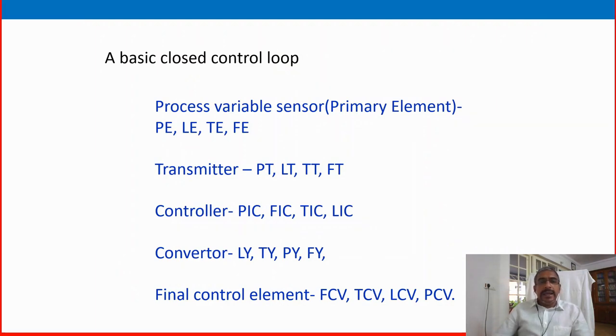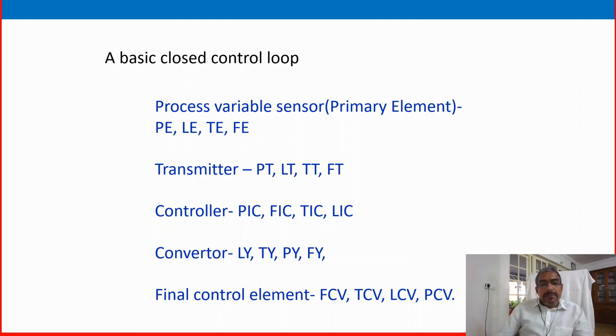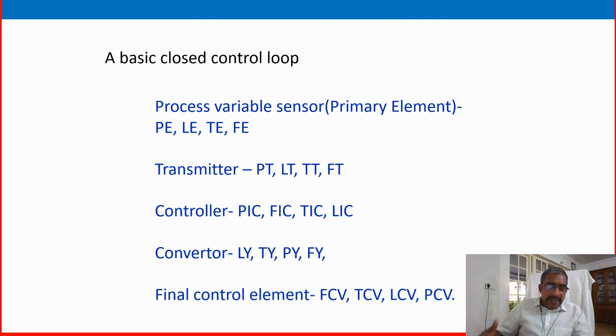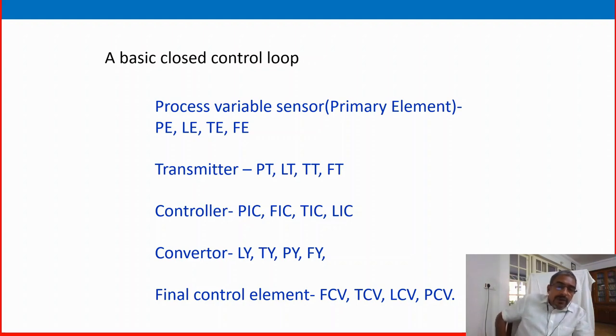Some examples of process variable terminology used in drawing sheets or in the process field: process variable elements are PE (pressure), LE (level), TE (temperature), FE (flow); transmitters are PT, LT, TT, FT; controllers are PIC, FIC, TIC, LIC; converters are PY, LY, TY, FY; final control elements are FCV (flow control valve), TCV (temperature control valve), LCV (level control valve), PCV (pressure control valve). Please review any existing P&ID you have — the next class will cover how to read a P&ID. You can read and understand from the engineering drawing or piping and instrumentation diagram how to understand this terminology. When you go to the field, look for any controller, transmitter, converter, sensor, and control valve.